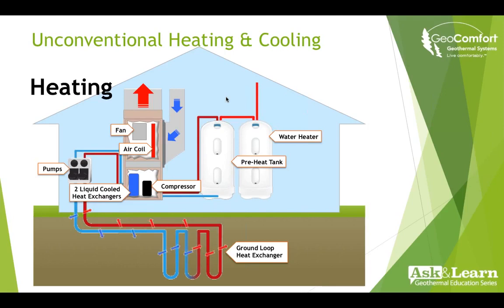Now we're going to take a look at the same system, but change modes to heating. The fan will pull cool air from the house across the warm air coil, warming the air up and discharging it out through the registers in the home. All of the same components are used—we simply reverse the machine so we can put heat into the house instead of taking it out. In this mode, we also share some of the energy we absorb from the earth with the preheat tank. So in both modes, the geothermal system is always preheating your water whenever it's operating.